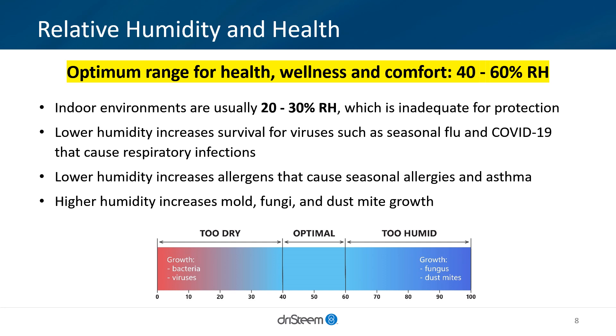Lower RH increases the survival of viruses such as seasonal flu and COVID-19 that cause respiratory infections. Lower RH also increases allergens that cause seasonal allergies and asthma. It is also important that RH is not too high. RH above 60% increases the likelihood of mold, fungi, and dust mite growth, which can all have a negative effect on human health.